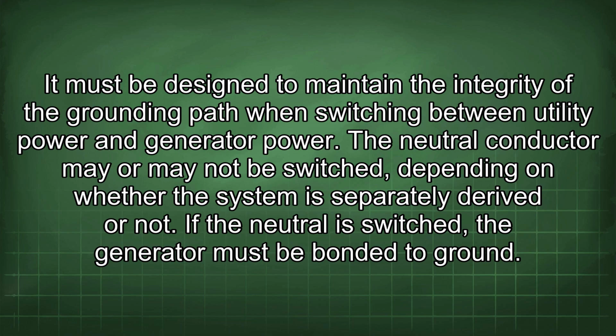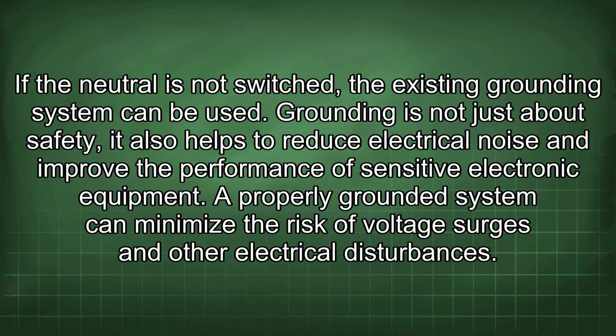The neutral conductor may or may not be switched, depending on whether the system is separately derived or not. If the neutral is switched, the generator must be bonded to ground. If the neutral is not switched, the existing grounding system can be used.